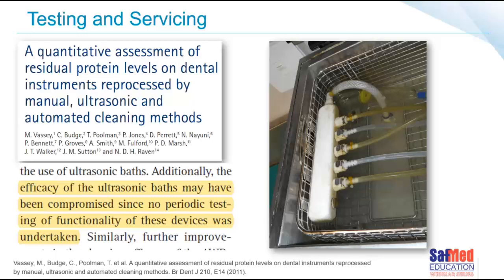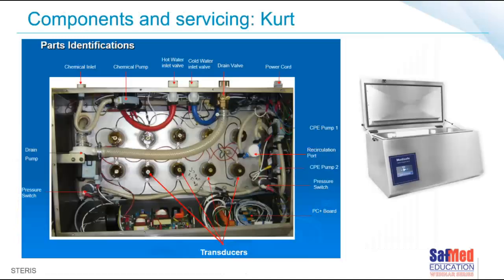So in the inner parts that you showed earlier, you end up finding it in certain pumps, which we'll discuss later as well. It's very important not to leave the water, as we mentioned earlier, because of the buildup of endotoxins. So we make sure it's empty, we dry it out, and we leave the lid open overnight. And it's not a storage area for anything else. We often need to store something away quickly, so we close the lid, put stuff on top of it, or put something inside it, and the rest of the packing we want to store ends up on top of the lid. So the lid definitely needs to be open when not in use.